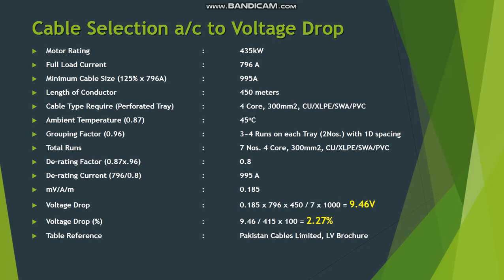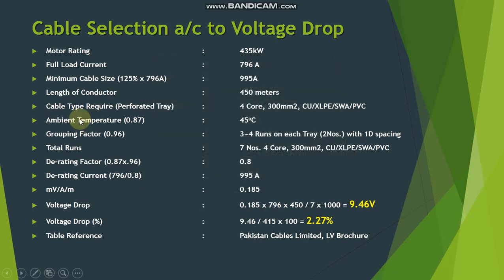For cable selection according to voltage drop, our motor rating is 435 kilowatts, full load current is 796 amperes, minimum cable size is 995 amperes, and the length of the conductor is 450 meters from motor to panel, which is quite long. The voltage drop must fulfill the IEC standard: less than 5% or between 2.5 to 5% under normal conditions, and 10 to 15% under motor starting conditions. The cable type we are using is 4-core 300mm² copper XLPE armored.